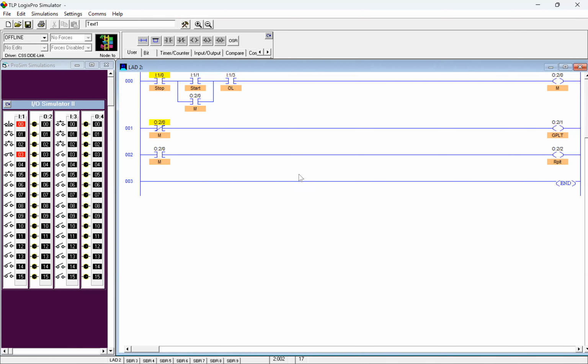That's just another way. You don't need to drive another control relay out there. You don't need to wire it in. The only thing I'd wire in is my stop, my start, my coil, my overload, and 2 lights. I'm done. I walk away. There's none of that memory circuit wiring that takes forever to do and all that. It's already done inside the PLC for you. Big, huge cost savings. And then if you add an HMI, a large HMI out there, you don't even need to wire the lights because they're all on the HMI.